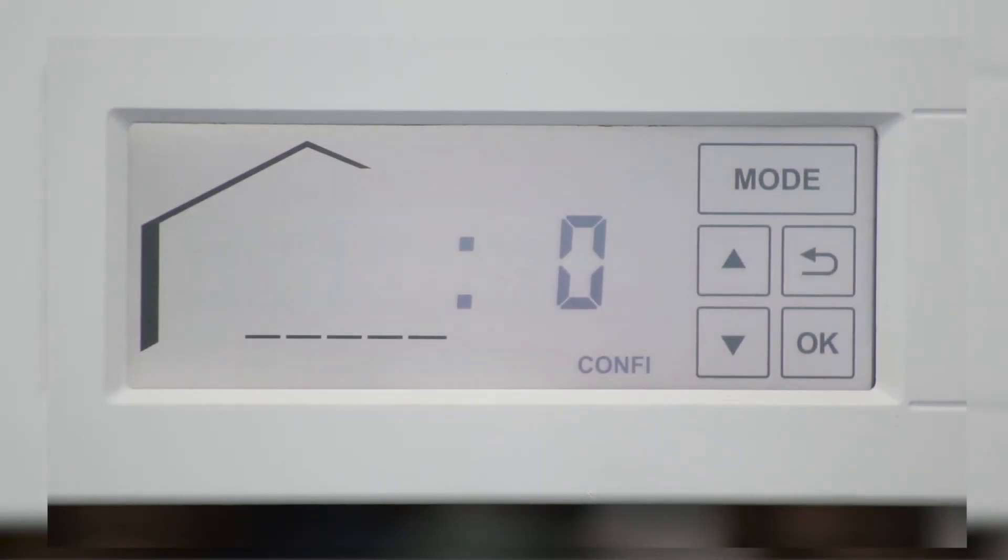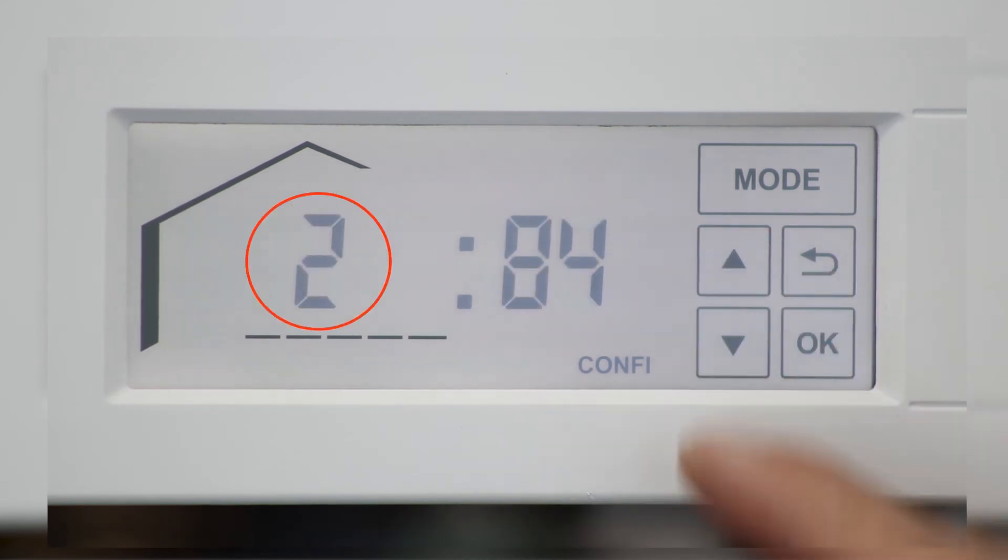The maximum heating output of your boiler can be adjusted according to the system requirements. Once in coding, use the up or down arrows to scroll to address 2. Pressing ok on address 2 allows you to make the necessary adjustments for your system.